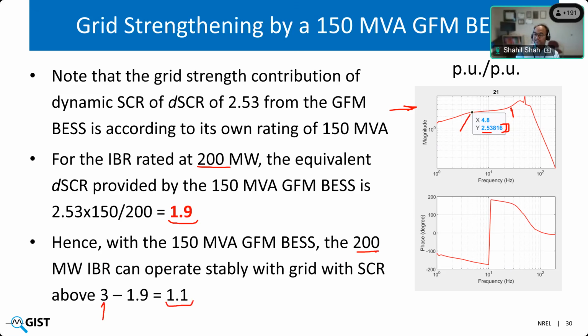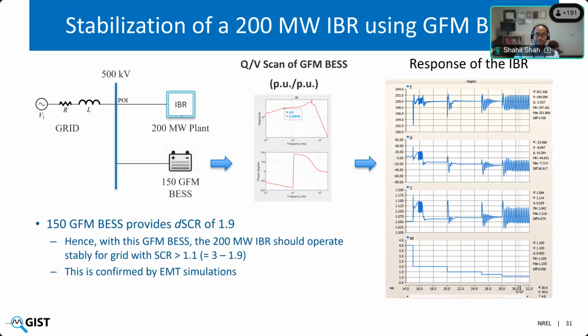So it should remain stable to such a significantly weaker grid, even though it was not without this BESS. And that is what we confirmed with time domain simulation. We connected this BESS at the same POI and then kept reducing the grid strength. And the IBR becomes unstable only when the SCR is reduced to 1.1, and it starts oscillating.